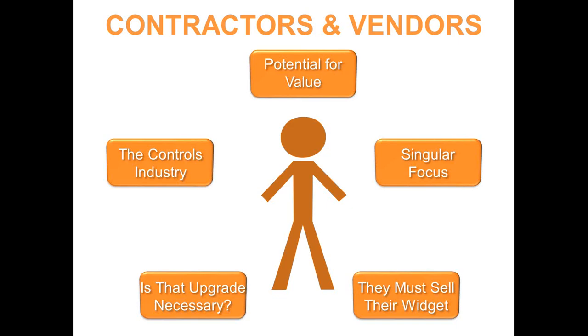So when you add to that the fact that the building engineer really has very little understanding of how those systems work, in other words, that control system. And I'm going to point out that if you asked your building engineer, in many cases, I would say probably 75 to 90% of the cases, to reprogram or set up a new sequence of operation for the controls in his or her building, the likelihood is that they would call the controls vendor and have them come in and do that.